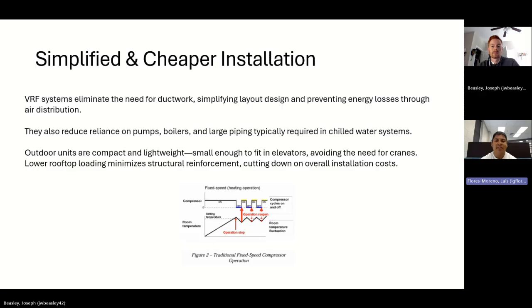Simplified and cheaper installation. VRF systems eliminate the need for ductwork, simplifying layout design and preventing energy losses through air distribution. They also reduce reliance on pumps, boilers, and large piping typically required in chilled water systems. Outdoor units are compact and lightweight, small enough to fit in elevators, avoiding the need for cranes. Lower roof loading minimizes structural reinforcement, cutting down on overall installation costs. Here for Figure 2, we have the traditional fixed speed compressor operation.